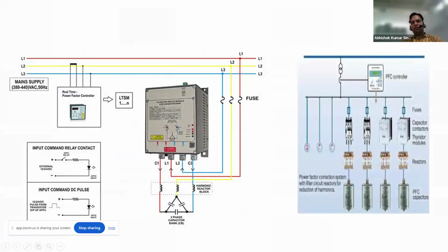Now this you can see. So an APFC panel is basically, this is a reactor, then this is a capacitor, this is a contactor, and this is a thyristor. So basically a capacitor can be controlled by a thyristor, or a capacitor can be controlled by a contactor. But the point is that the correction time of a thyristor is very fast, whereas the correction time of a contactor is slow. Fast means it's in milliseconds, and slow means it's in seconds.